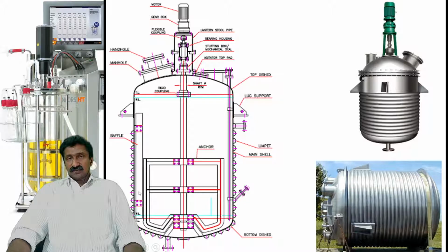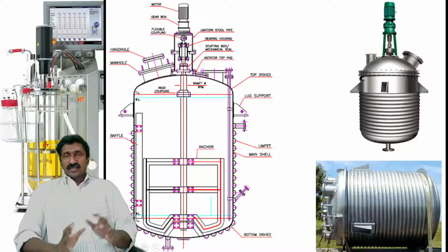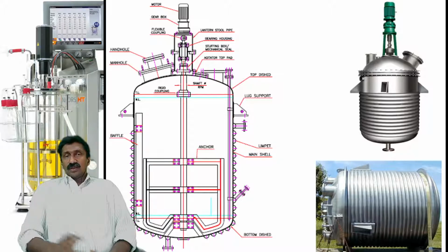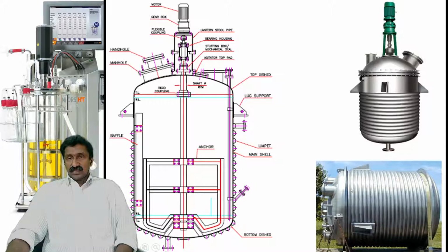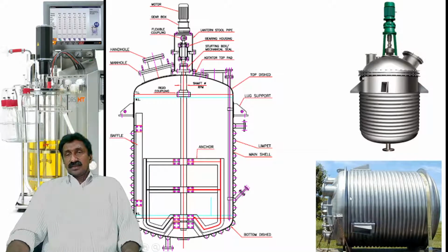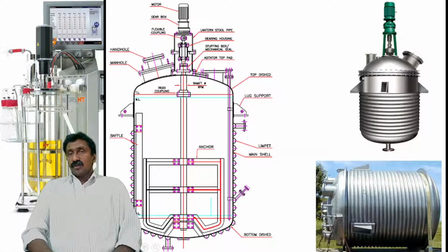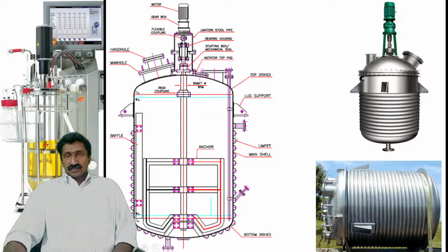So this is the fermenter vessel, over which the pipes were, or half pipes means it's only a hemicircle, and the side that is facing the vessel wall is a flat one because it's actually welded to that container, and only a hemicircle pipe is represented over here. It is not a complete pipe. It is not cylindrical. Okay. So the side that is facing the vessel wall is flat, and a cross section can be represented like this.